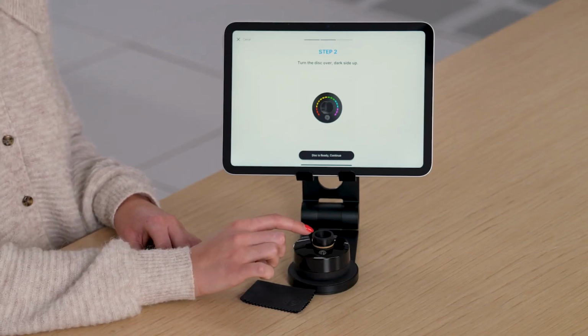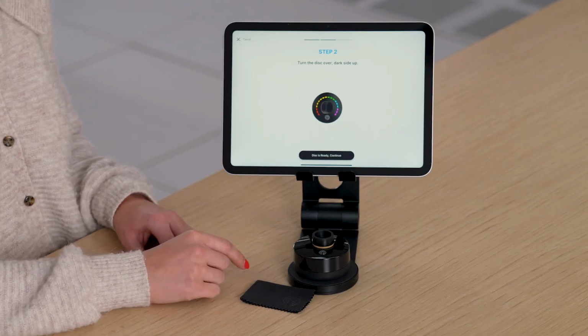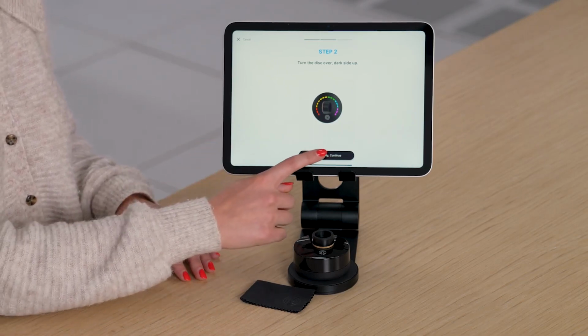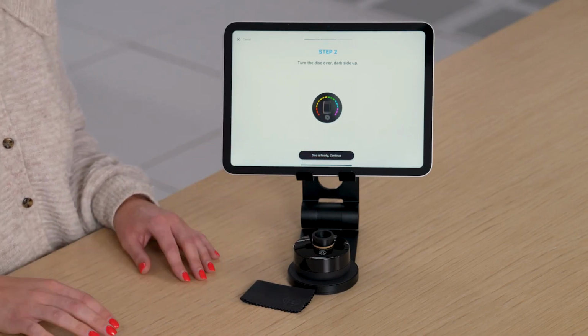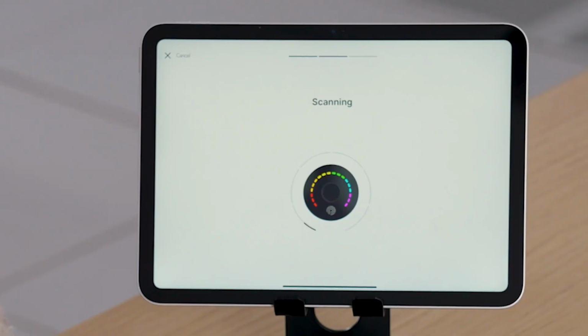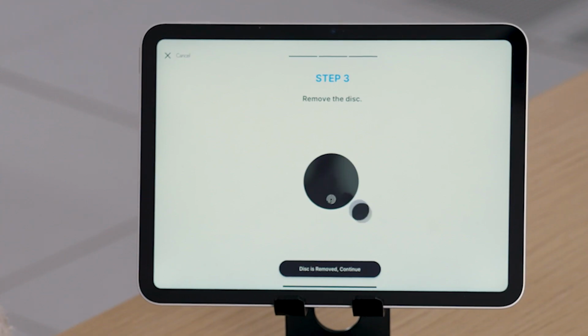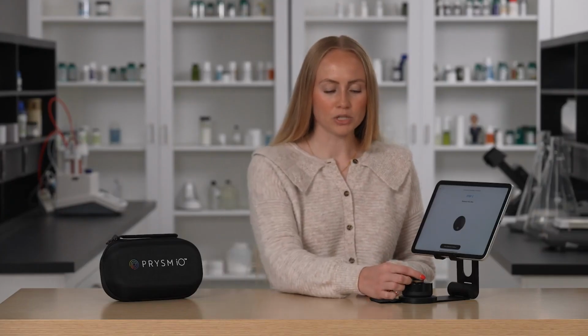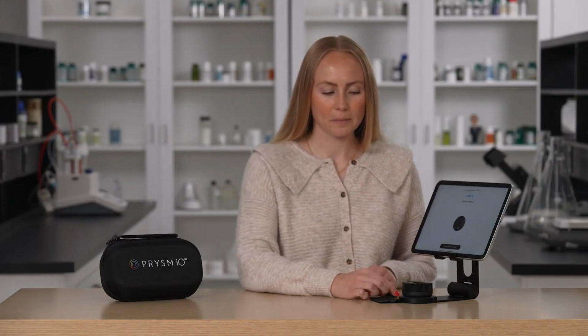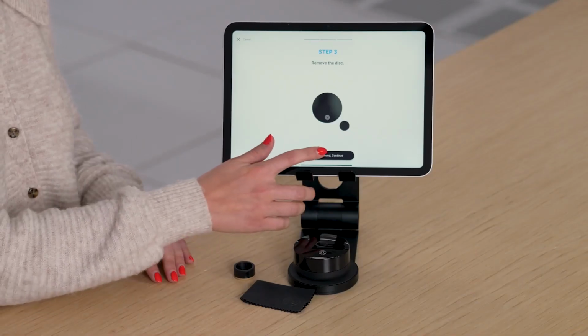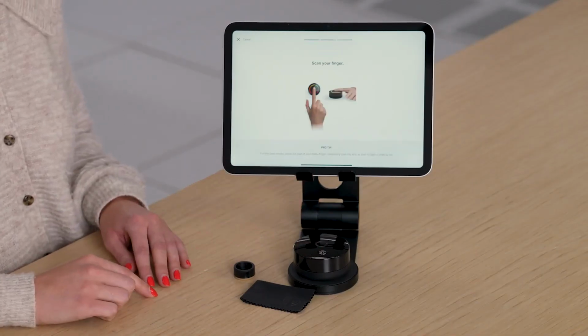You should be able to see that 4-digit code facing up. Once you've done that, press Disc is ready, continue. We are now doing a second 15-second scan. Once that is completed, the app will prompt you to remove the calibration disc. The last step in calibration is going to be to scan your finger.